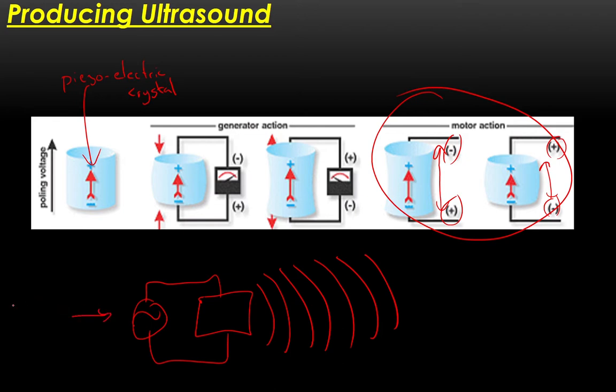Now if I make that, let's say just for argument's sake, 50 kilohertz, then what I'm going to get there is a pulse of ultrasound. What's even more useful about piezoelectric crystals is they actually work in reverse. So this was motor action, they also have a generator action. So if I have incoming sound waves and I apply them to a piezoelectric crystal, then what I get out is an alternating current and that will again alternate with the received waves. So I can use this to receive pulses. I can send out the pulse of ultrasound and then I can listen for the echo back at my transmitter or transceiver.